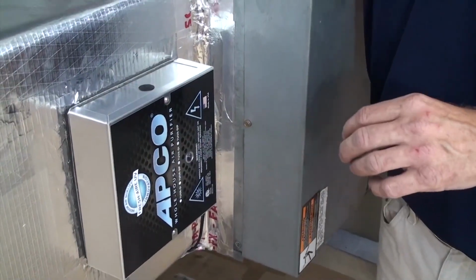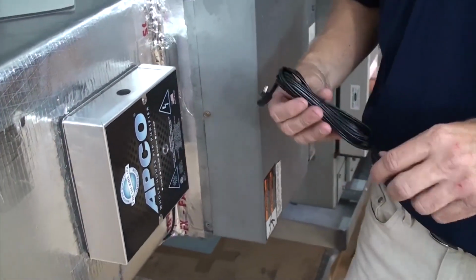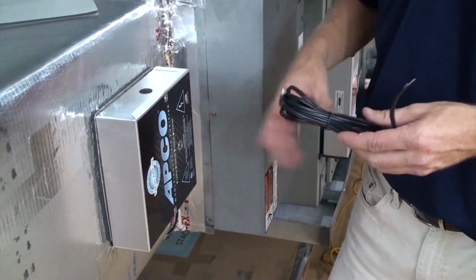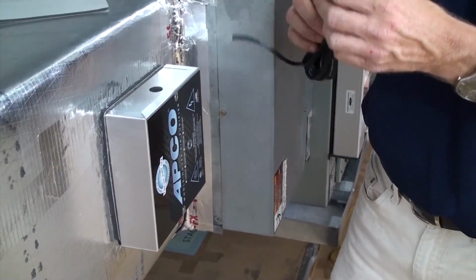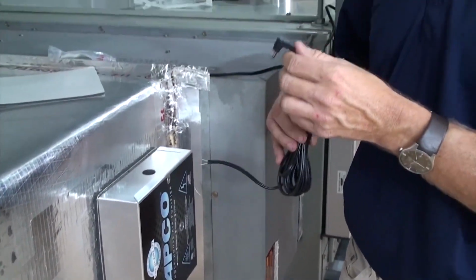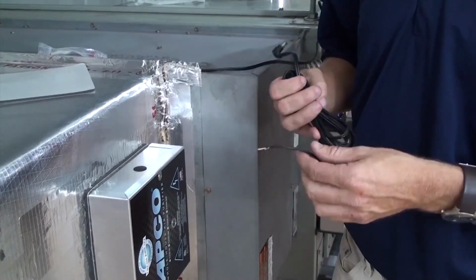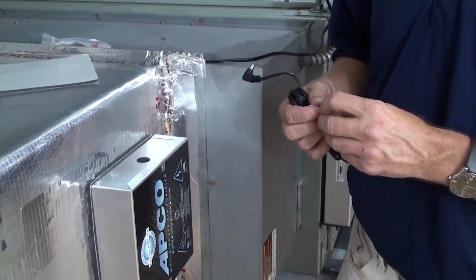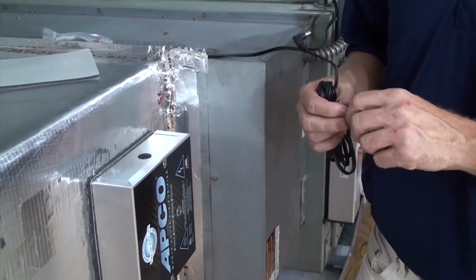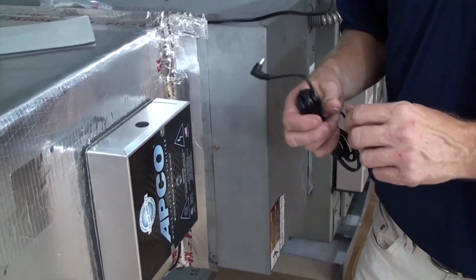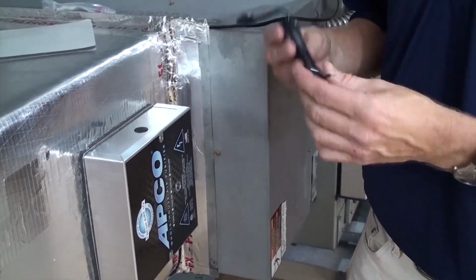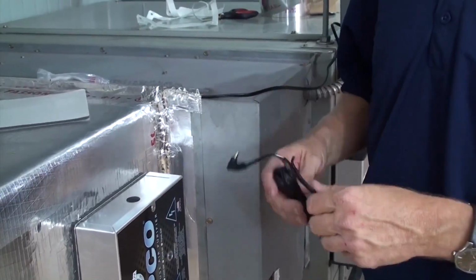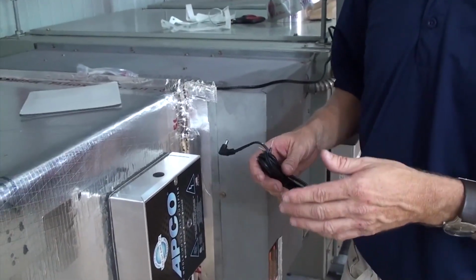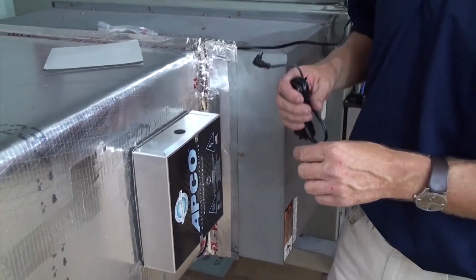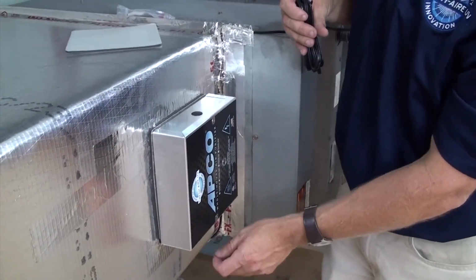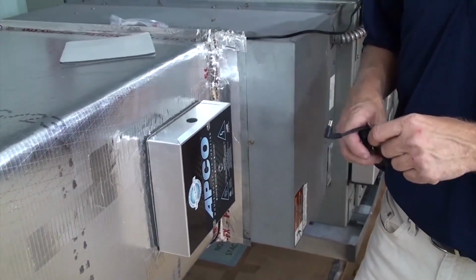In this case we have the TUV-APCO-ER, which is the 24 volt model. In that kit you have the pigtail disconnect, which wires directly up to your 24 volt transformer. You can either use the factory transformer or add a second transformer directly to power up the APCO unit. On the APCO SI and DI line voltage models, those have a fixed cord coming directly out of the bottom to wire to your line voltage.